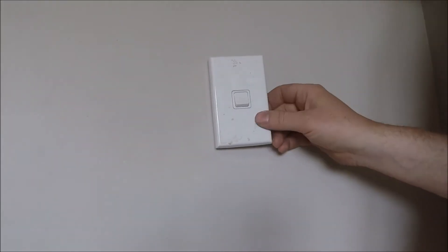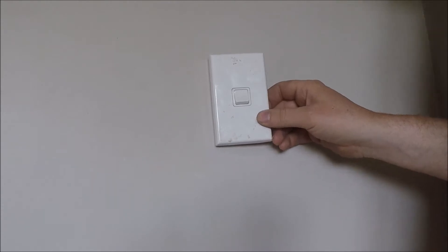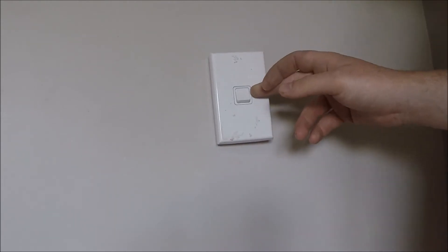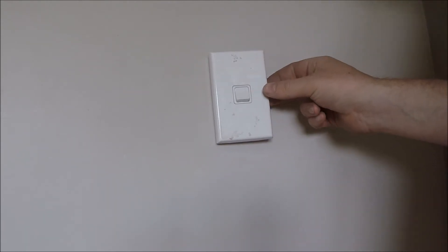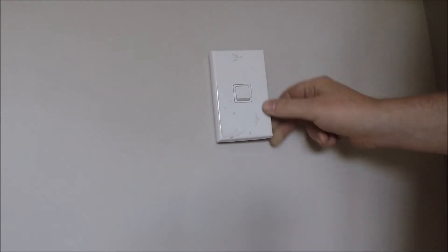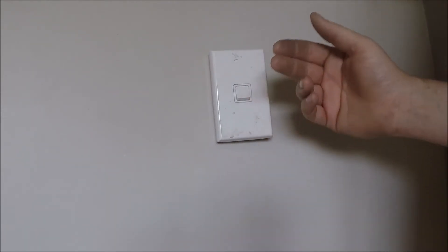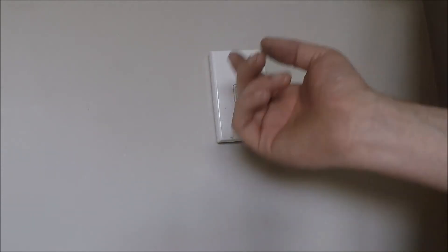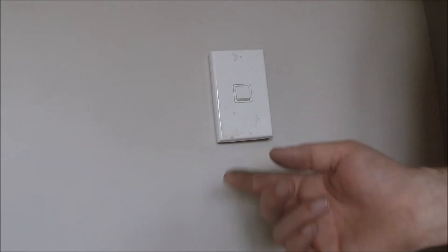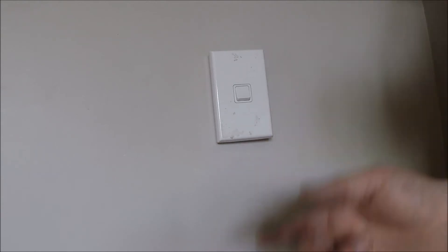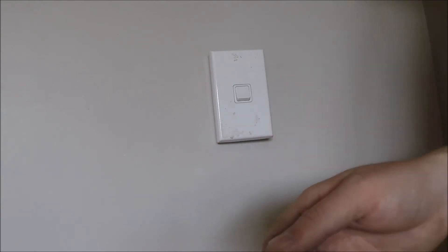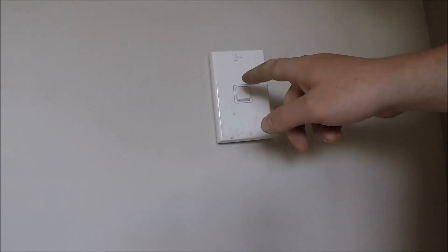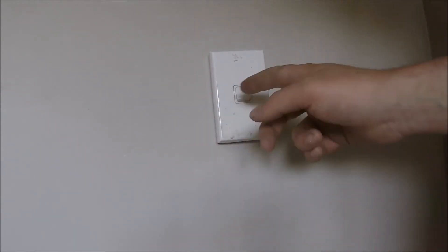The best method to use is test between phase and earth. But obviously there's no earth available here. If you are concerned, you can run an extension lead from a socket nearby, and use the earth pin of that lead when testing between phase and earth.